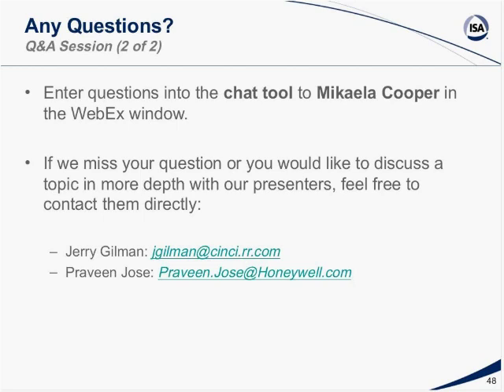Go ahead and repeat that question and make sure I get it right, Michaela. Let me pull that up here. Does the code require the burner management/safety system to protect against factors that contribute to furnace implosions? Yes, it's in Section 5 of the code, where it has all specific requirements for implosion protection, and the requirements for that is defined in the code in 85.